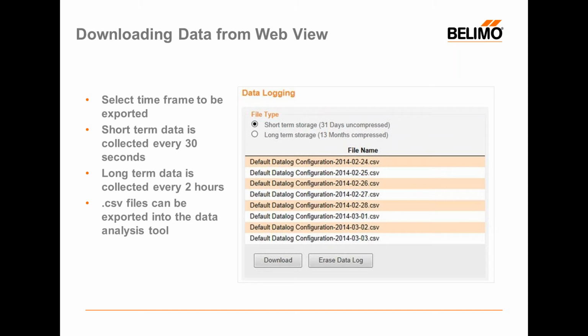These files will be stored in the valve. You will have up to 31 days of uncompressed short-term data and up to 13 months of compressed long-term data. This is first in, first out, so once you reach the 32nd day, the first day that was data logged on the short term will start to move out, and you'll have the second day. And with 13 months, once you exceed 13 months, the first month will be deleted, and the next month that's being data logged will be stored in the valve itself.